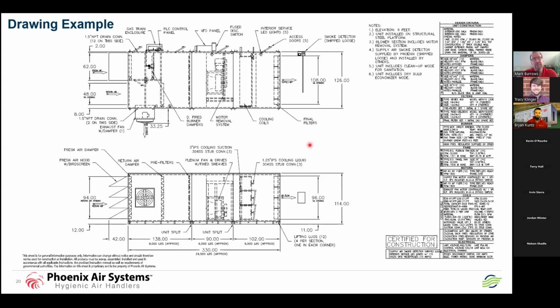And keep in mind, at the plant, these are fully tested. We certainly can't put a refrigerant through it, but we can certainly check all the IO and whatnot. We'll fire off the burners to make sure at the plant they're working properly, such that when we go to the job site, the startup tech would go out, start these up. He's not troubleshooting. The shop's already done that. His job is pretty easy, basically just making sure the wiring is correct from the field wiring, and then he'll definitely test the unit, full-blown test at the job site.